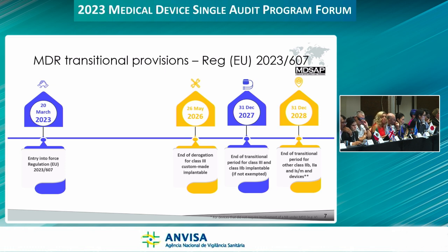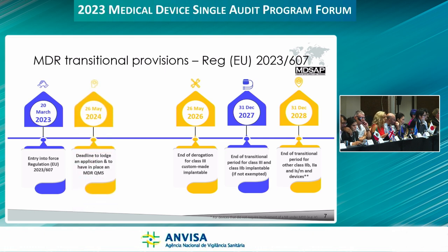What's missing here are actually the most important dates to keep in mind, especially for manufacturers, and to ensure that notified bodies have the time to process your applications. The upcoming deadline is 26th of May, 2024, to actually lodge an application with a notified body and to have in place an MDR quality management system. This is critical if you want to be transitioning to the new regulations, as well as to make use of the extended transitional provisions.